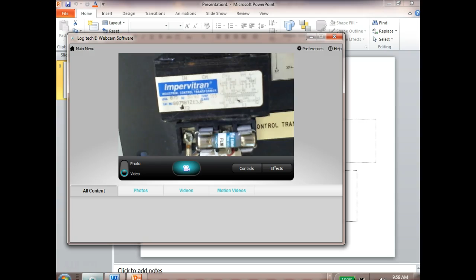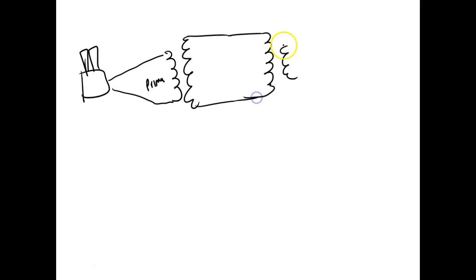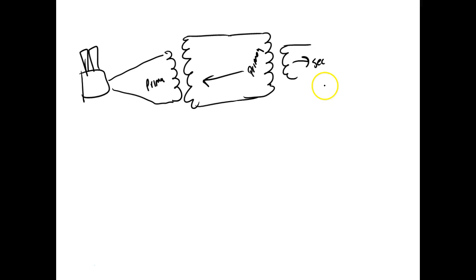Yeah, the load. So your primaries always point back toward the source of the power, and your secondaries always point back toward the load. It doesn't mean it's necessarily connected to a load, because especially in our power grid, we have transformers connected to transformers, right? So if the power company is sitting over here with their smokestacks, and they come up here and connect to a set of transformers, this right here would be the primary. Then we might step this up, and it might come over to another transformer, and we might step it down. Well, this right here is still the primary because it's pointing toward the source, and this right here is the secondary because it's pointing toward the final load, whatever these transformers are going to end up driving.